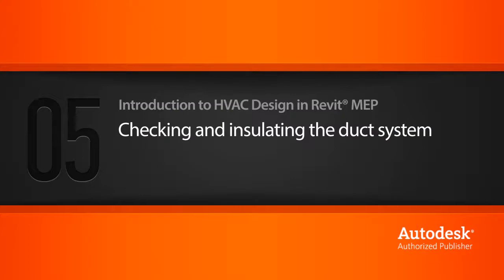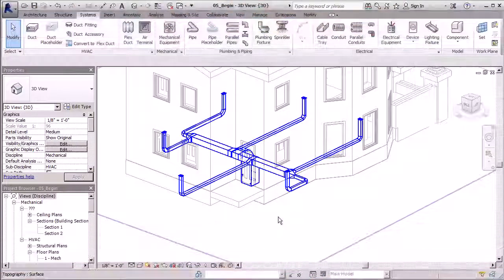Okay, so now that my system's in place, there's a few things I can do. Before we finish it off by adding insulation, let's make sure everything is set. I want to check my connections. I want to make sure everything's connected right. I don't want to have any open ends. And I want to also see if there's any pressure loss in my system. And if not, then we can actually move forward and wrap this up with some insulation.